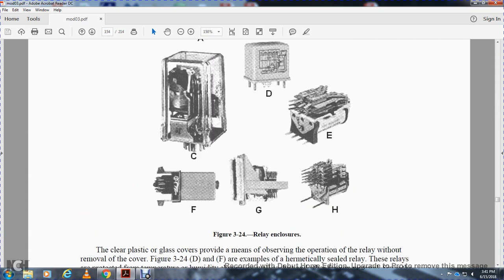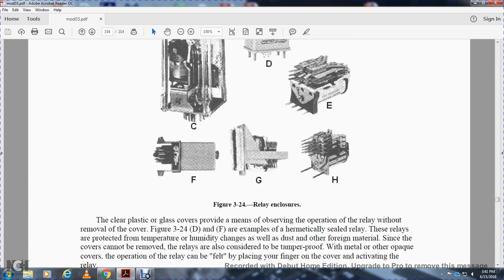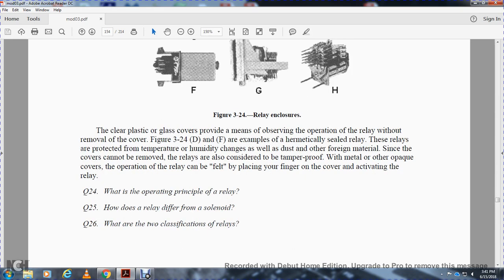of the cover. In Figure 3-24, D and F are examples of the hermetically sealed relay. These relays are protected from temperature and humidity changes, as well as dust and foreign material. Since the covers cannot be removed, the relays are considered to be tamper-proof. With a metal or other opaque cover, the operation of the relay can be felt by placing a finger over the cover during the activation of the relay.